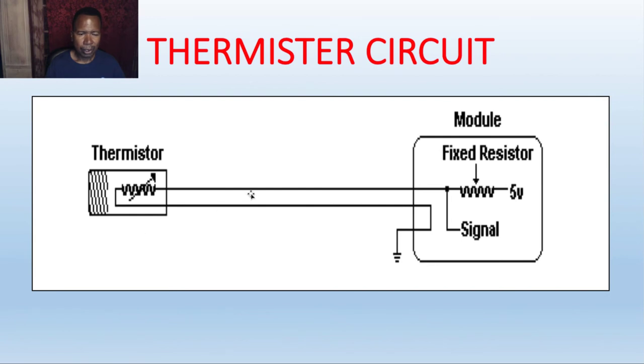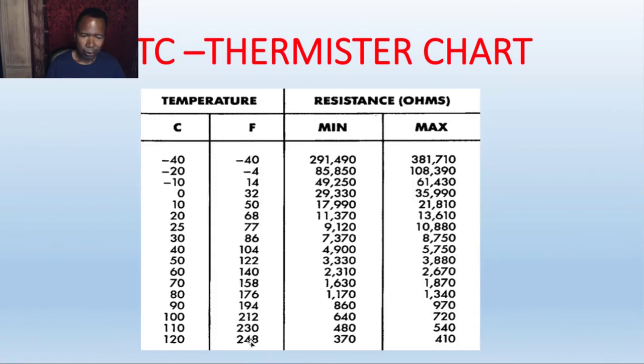So what it could be is this wire, 5 volts touching ground. I'm going to see a low voltage on this line here. These 2 wires touching together, this one and this one, also gives signal wire low. Now remember, that's a short, low resistance. Look at that, 248 degrees, default number.